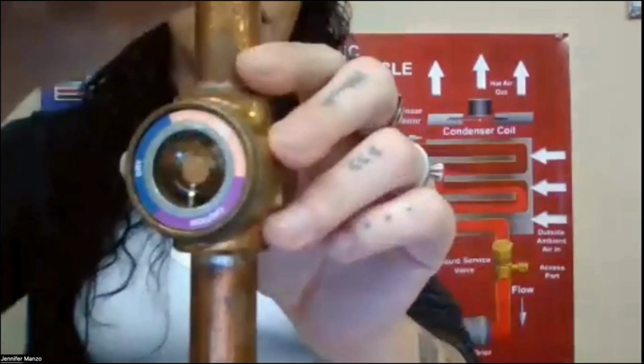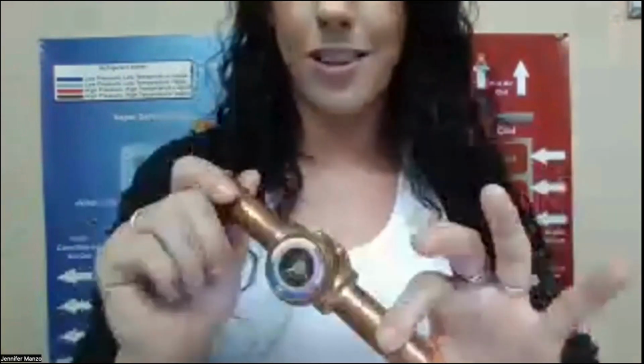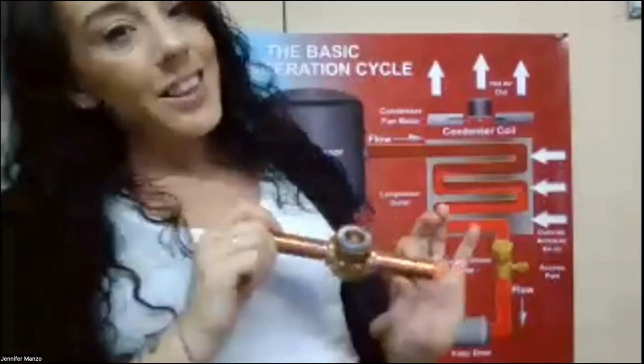So what you'll see as you're charging the system in that glass is you'll see the liquid refrigerant, and when you see it, it will be bubbling, boiling faster than anything you've ever seen. Then the second you add the correct charge of refrigerant, it will clear, immediately, just whoosh and clears. And once your sight glass is figured correct -- can we always say that? No. But if it's put on the correct system, you can actually tell that your charge is correct by looking at this. And that's a super gauge.